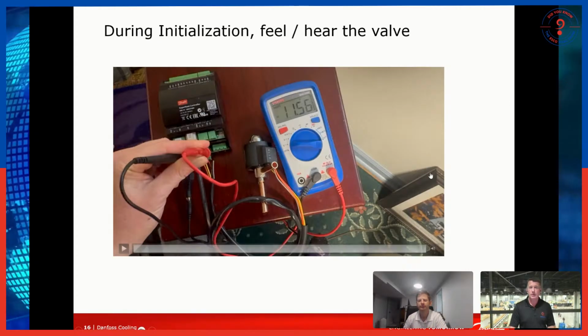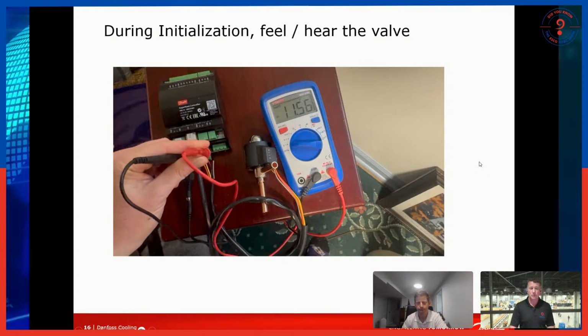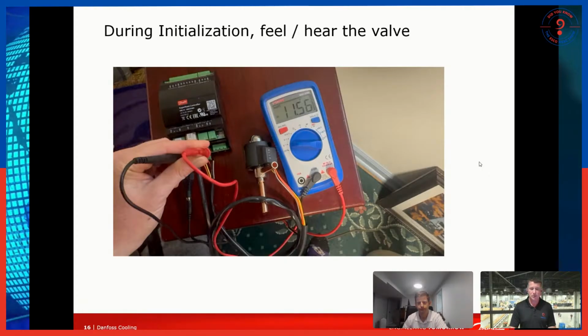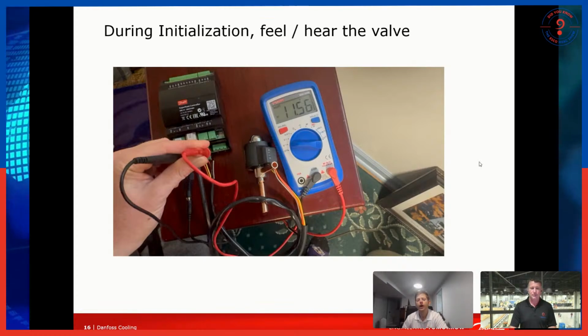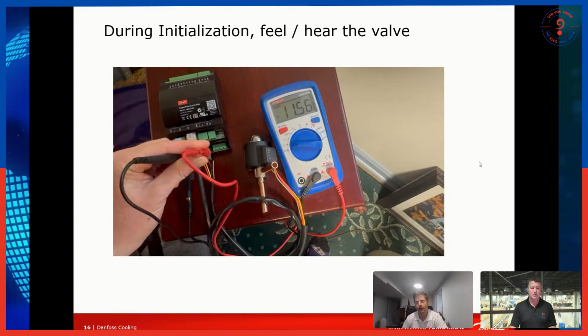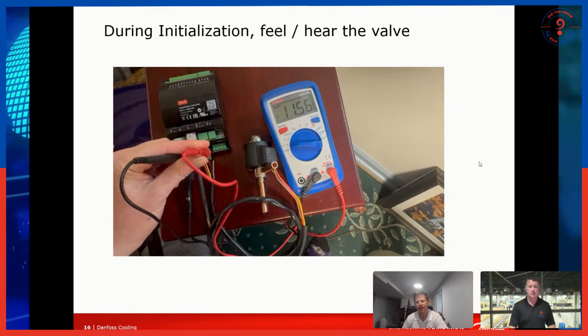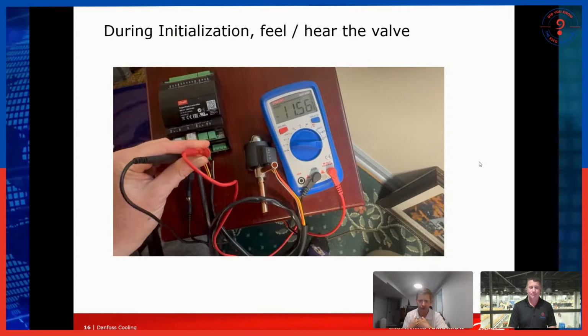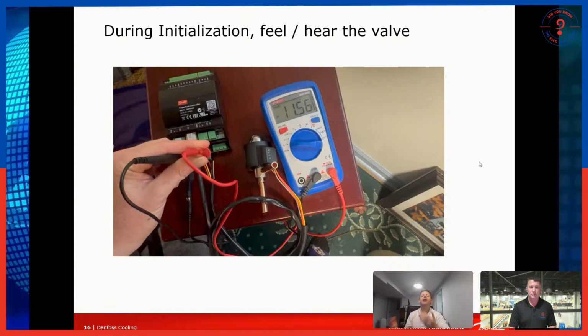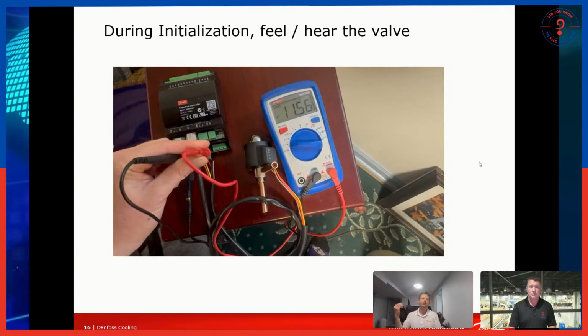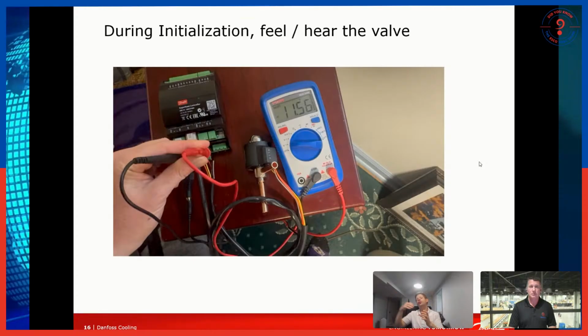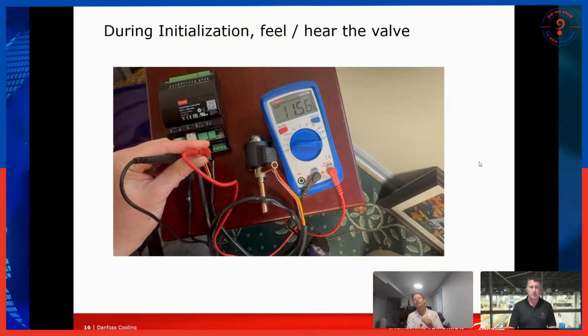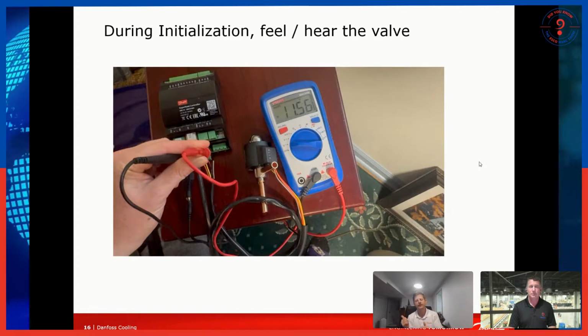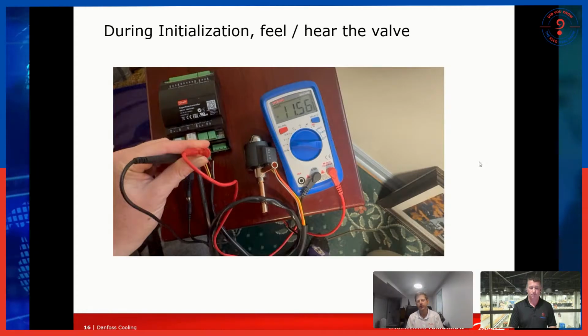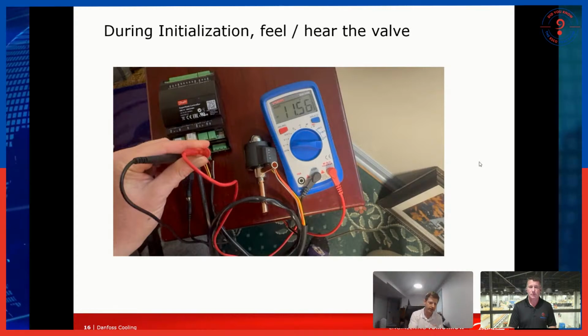Now, on our temperature thermistor and our pressure transducer, will we still see a 12 volt DC signal, or will it be something different? So most of the transducers are not going to be 12 volts. The most common ones that Danfoss sells are at 5 volts, but there are different ones out there. The way the most common one that Danfoss sells works is you send a 5 volt signal from the controller to the sensor, and then the sensor sends back a 0 to 5 volt signal based on what the pressure is, 5 volts being the highest pressure, 0 being the lowest.